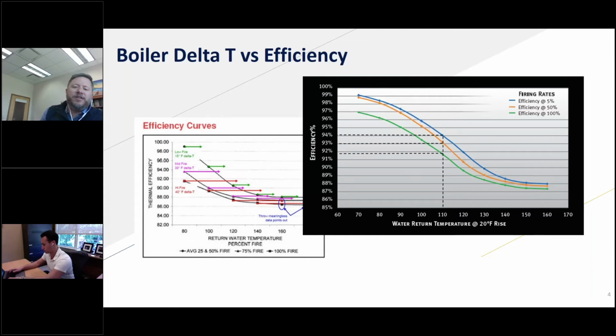But one of the things, if we look at this chart on the right, that's all based on a 20 degree rise. So in my example that I just said, if we're going to try to do a 30 or 40 degree rise, really what we have to start looking at is the chart on the left. It's a little bit small, but what that is really saying is that the 20 degree rise gets us up into that 98, 97, 98, 99% efficient operation. At the same return temperatures, with a 40 degree rise, we're actually seeing that efficiency degrade down below 92% efficient.